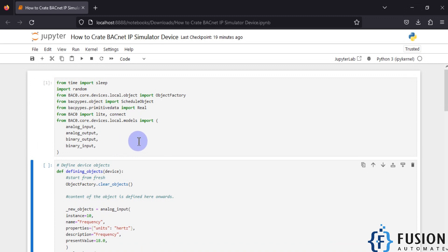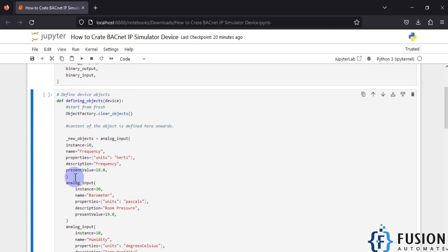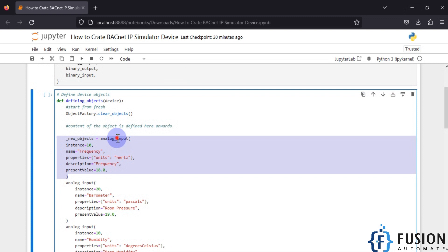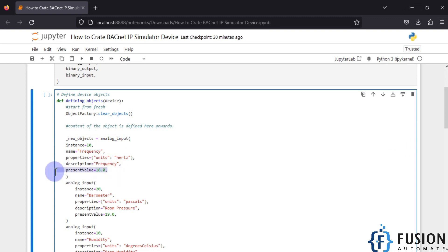If you have worked with OPC protocol or Modbus protocol, we have some tags and the tag values are updating and we read those tag values for analysis. In the BACnet protocol we don't call it a tag — we call it an object. This is how an object looks: our first object is an analog input type of object, the object ID is 10, and the object name is frequency. You can select the unit of that object and provide a description.